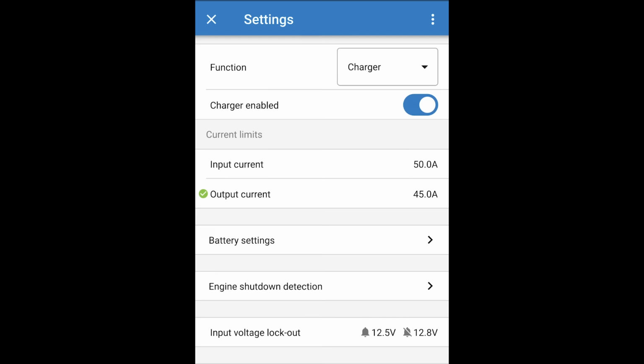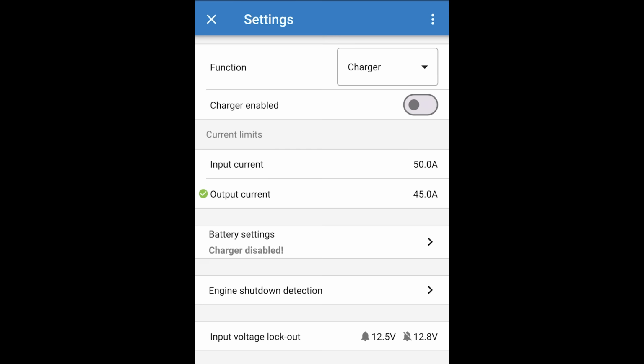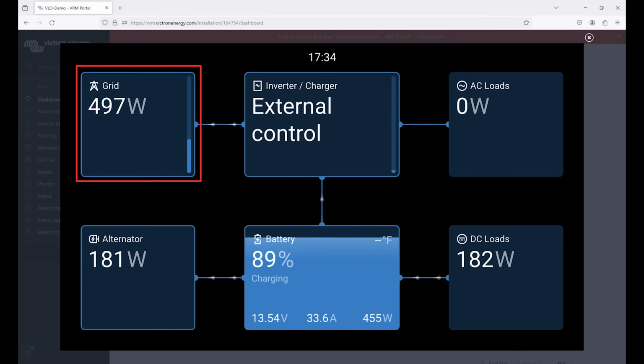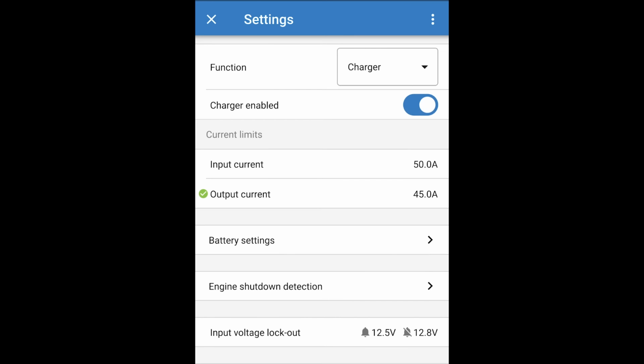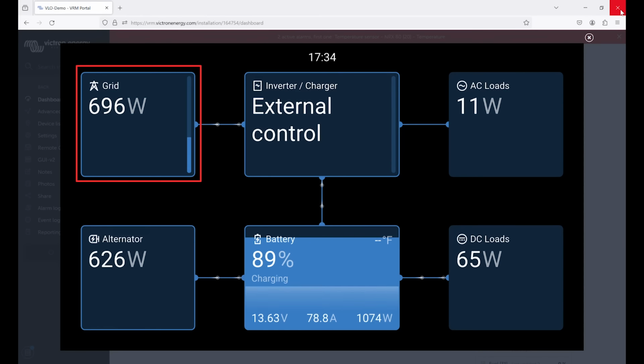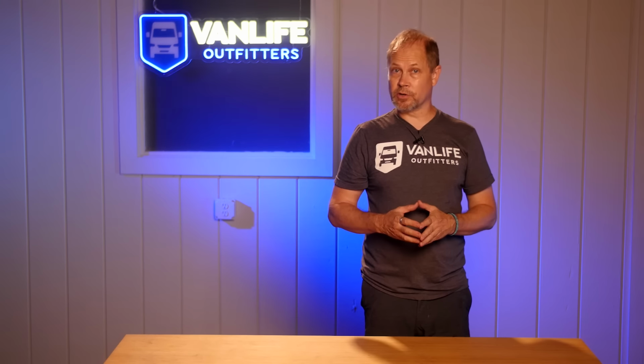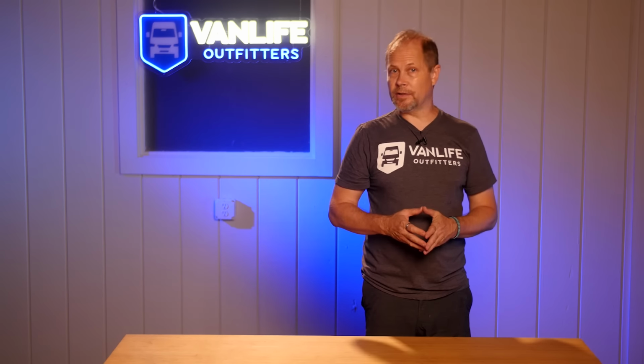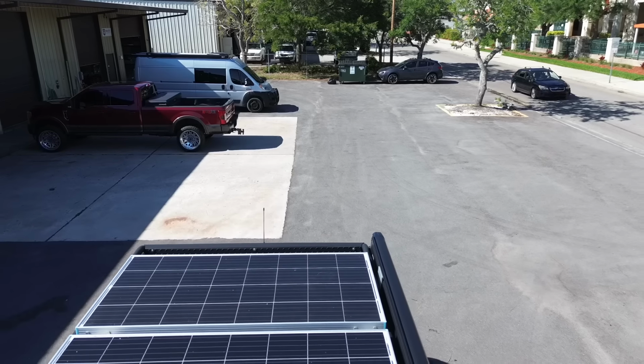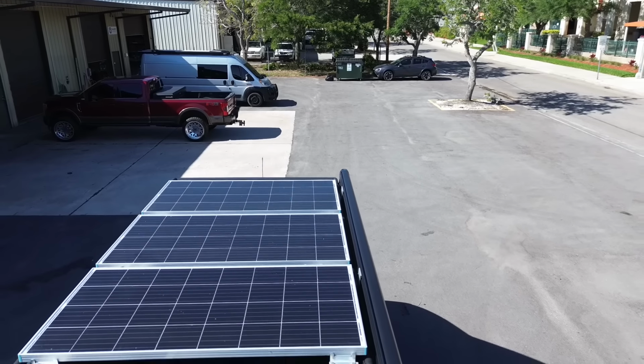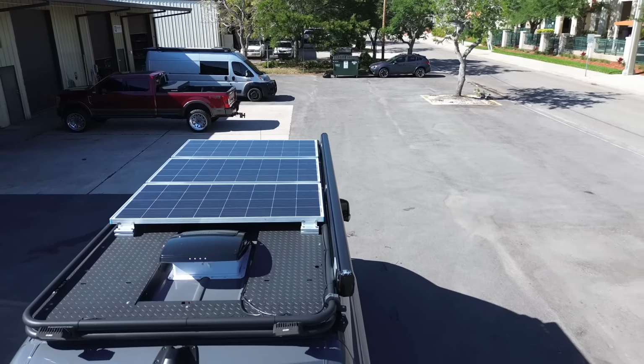Now, if I cycle the Orion XS off, you'll see that the inverter will actually pick up the entire load up to 80 amps. And then if I turn the Orion on, it will return to just filling in the gaps and so on and so forth. The same kind of prioritization would occur if we had solar power. In other words, the system through DVCC will prioritize solar power over shore power, free power over metered power.